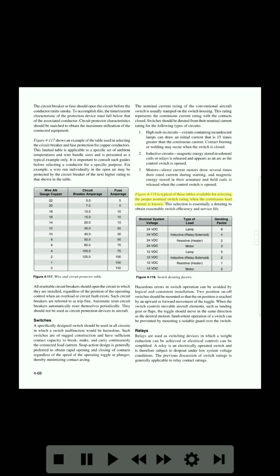Figure 4-118 is typical of those tables available for selecting the proper nominal switch rating when the continuous load current is known. This selection is essentially a derating to obtain reasonable switch efficiency and service life. Nominal system voltage. Type of load. Derating factor. 24 VDC, 24 VDC, 24 VDC, 24 VDC, 12 VDC, 12 VDC, 12 VDC, 12 VDC. Lamp, inductive, relay solenoid, resistive, heater. Motor, lamp, inductive, relay solenoid, resistive, heater, motor. 8, 4, 2, 3, 5, 2, 1, 2. Figure 4-118.